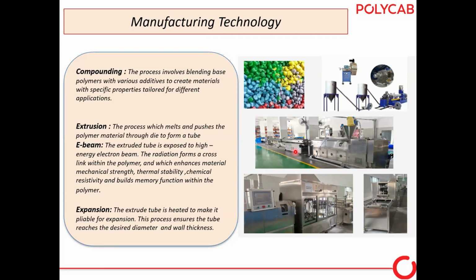After compounding, the extrusion process. So we have the compounding machine, and we have the extrusion machines. We extrude the tubes as per the requirement of the joint. If it is 400 square mm, 300 square mm, according to voltage class, we extrude that. E-beaming is very costly. If you compare e-beaming and chemical curing cable accessories, e-beaming cable accessories are costlier than chemical curing. But we do all our cable accessories with the e-beaming technology.